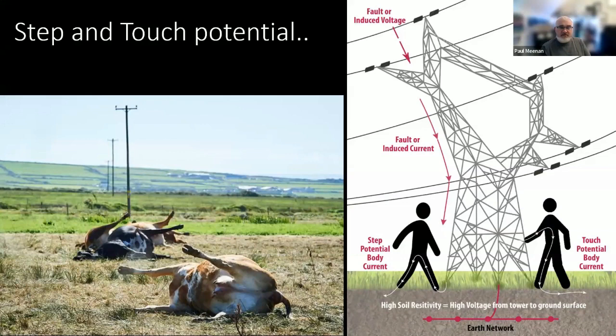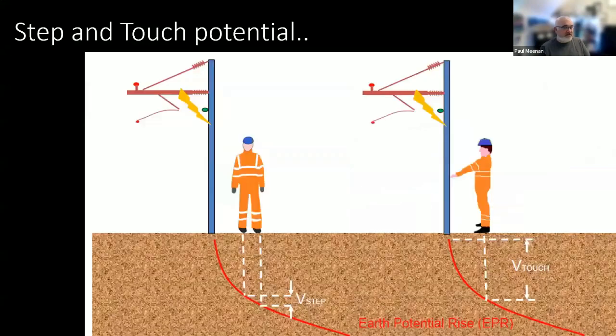In Ireland, we have a lot of problems with dewirements where they kill our beloved cattle. That's an incident in Ireland from an overhead pole that dewired. Cattle obviously can't take step voltages. So it's something to be mindful of when you're designing an earthing system. Have you considered your touch potentials? Have you considered your step potential, especially on high voltage systems? And there's some good videos online that will help explain that visually further.